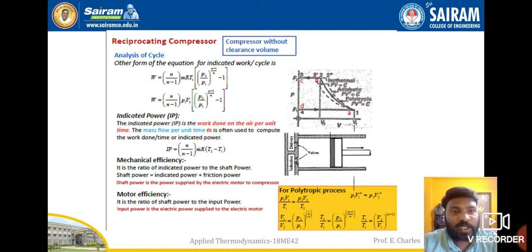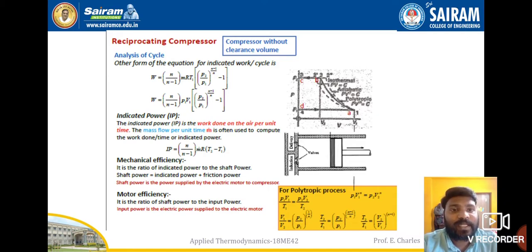Next, we will see some terminologies used in reciprocating compressors. The first one is Indicated Power, also called IP. Indicated power is the work done on the air per unit time. The mass flow rate is used to compute the work done per unit time. The formula for indicated power is: IP = n/(n-1) × mR × (T₂ − T₁).